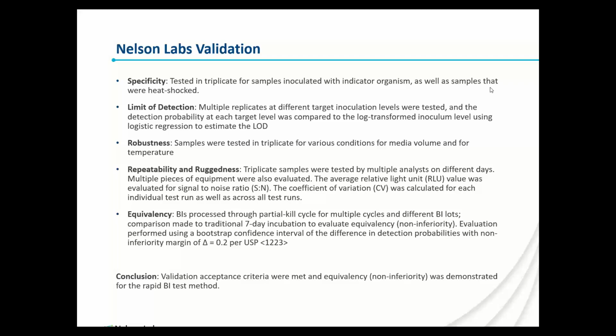So the conclusion of this validation was that validation acceptance criteria were met and that equivalency or non-inferiority was demonstrated for the Rapid BI test method, which is great. That means that this test method is validated and able to be used and is an approach that is in alignment with the guidance that's given in USP 1223.